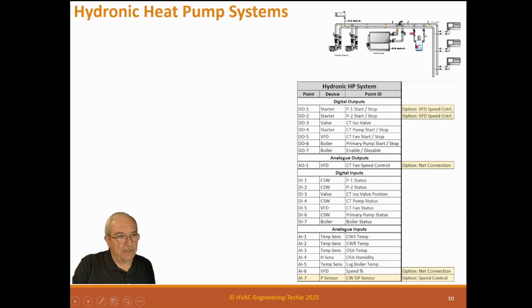The reason for this is because we use side stream boilers, so the full flow does not run through the boiler. The reason is boilers, at least water tube boilers, need to have a minimum discharge temperature so that we don't condense on the boiler tubes. So you may have 100 GPM running through here, and you may only have 30 GPM go through the boiler, and it may exit the boiler at 130 degrees. This will be balanced, so when it's on, this boiler can take cold water and leave it at 130 degrees, and then it mixes with the water here because this is a side stream boiler. So this may get it up to 75 degrees. If this is 60 degree water coming down, this little bit of water comes in and leaves at 135 degrees, and this 135 degree water mixes with the 65 degree water, providing us the set point we want. So that's why we do it that way.